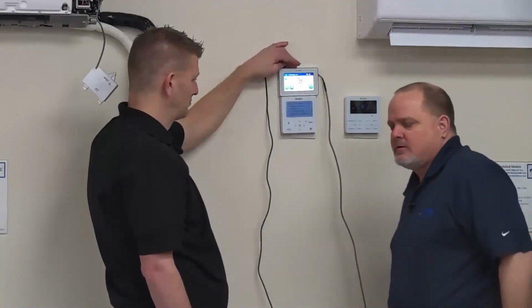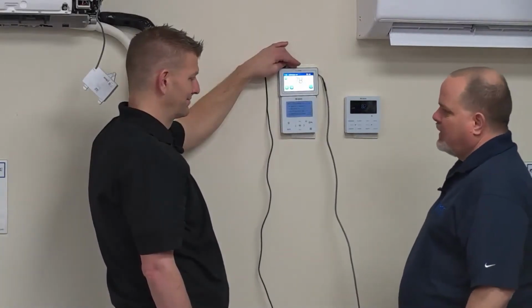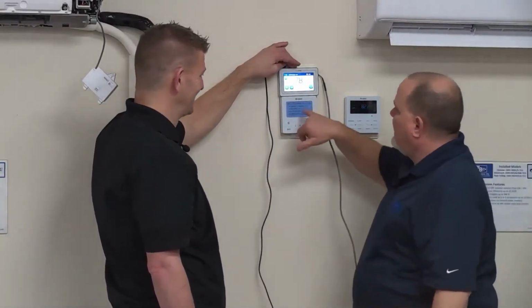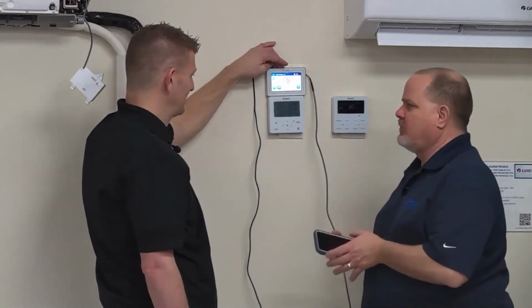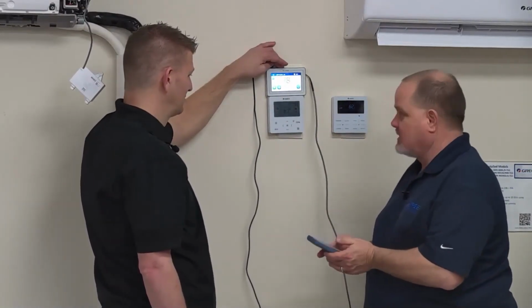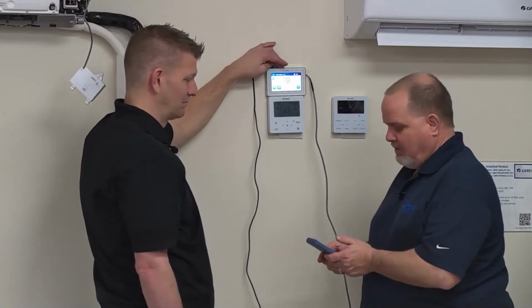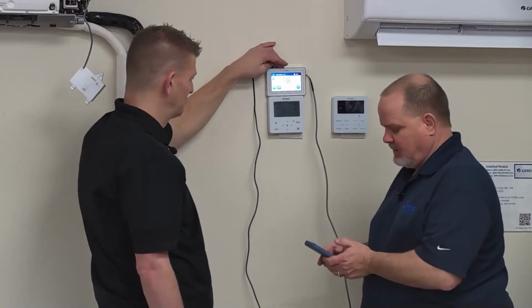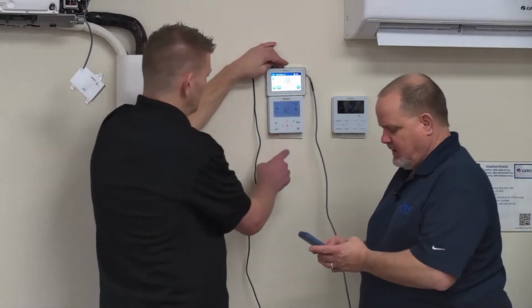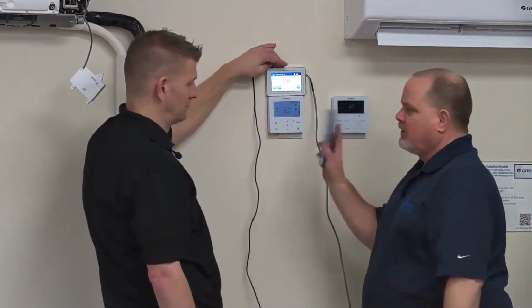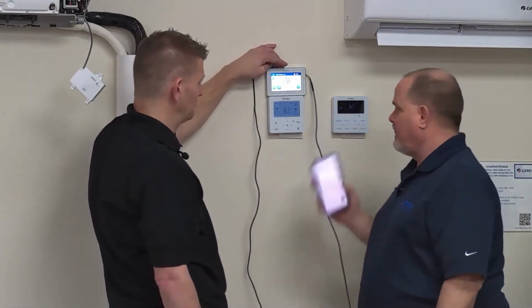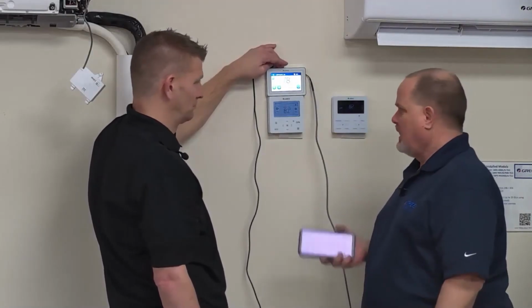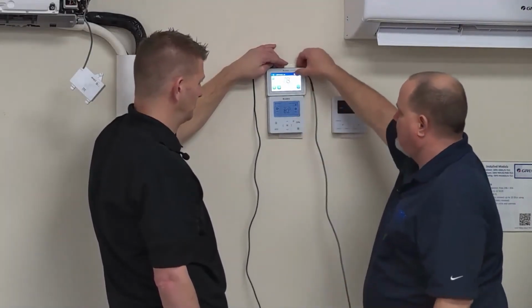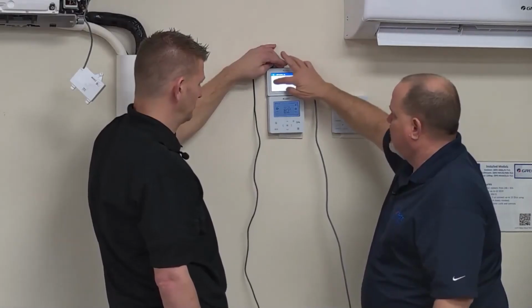We've seen in here we're way up in the 300s. My math is horrible, okay? I only have a 2-digit display there. I can't give you the full step. So it is 1 to 20, meaning you got to bust out the calculator. 16 times 24 equals 384 steps. That's what that controller is telling you. It doesn't tell you the actual step like this one will tell you.